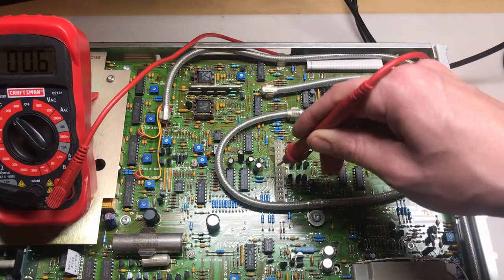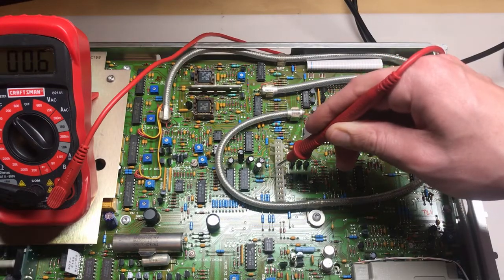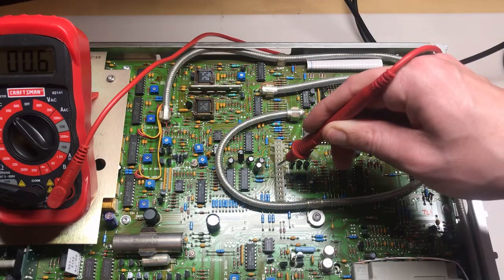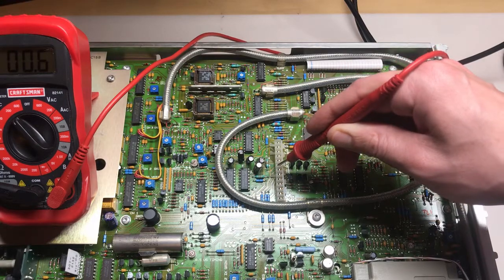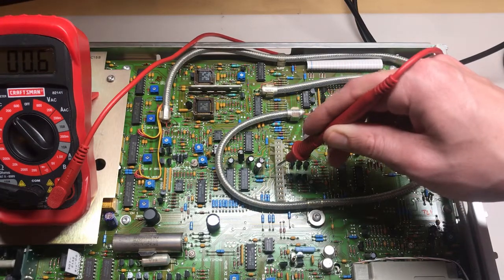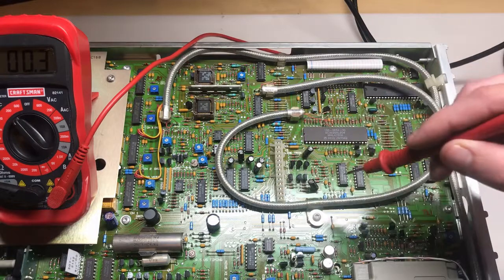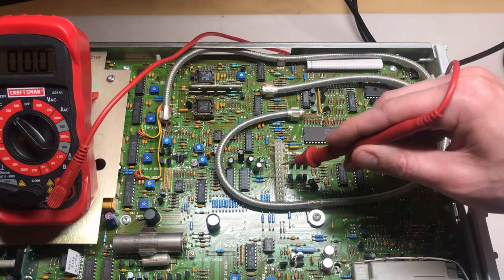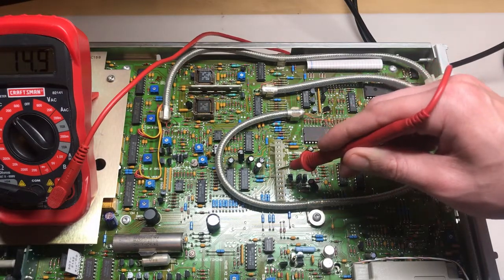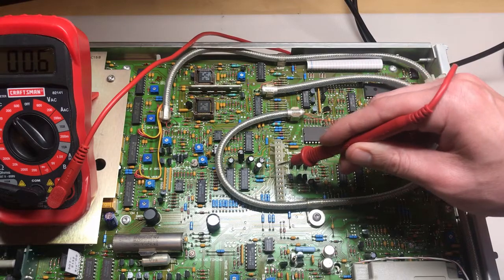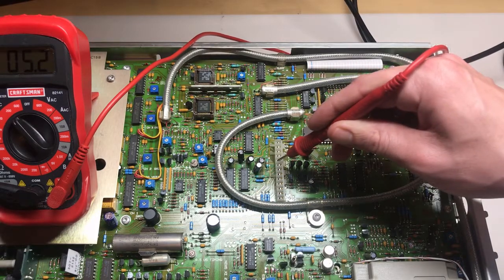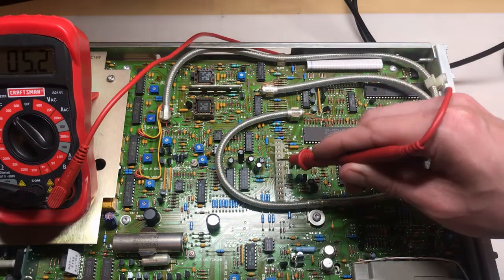One other thing to note, I know that there is a fan in here and it's not spinning. So either it's missing a voltage or the fan's dead. So that's another thing to note. So anyway, we're missing the minus 15 so far. Let's keep going. Next one should be minus 5. Sorry, I lost track. Positive 15. Minus 15's missing. Here's minus 5. That one's there.